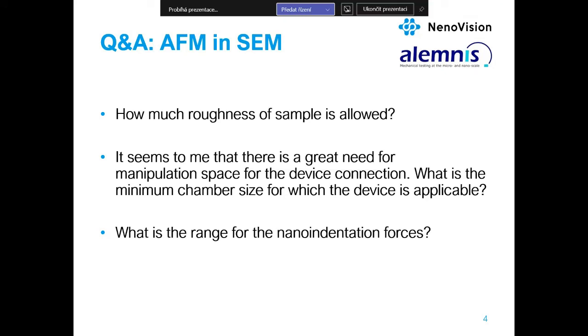The third, what is the range of the nanoindentation forces? So while the nanoindentation module is mounted in LiteScope, the recommended indentation force is up to 16 millinewtons. If it is standalone, Nick can answer the question. Yes, if you upgrade to a full Alemnis system, you can then change the load cells. So you can have either a 500 millinewton max load, a 1.5 Newton, or a 2.5 Newton. So we actually cover a very wide range of loads. With the LiteScope setup, you can get up to 16 millinewtons. And if you need a higher load, then the best thing is to upgrade to the full Alemnis system. So you get the best of both worlds.